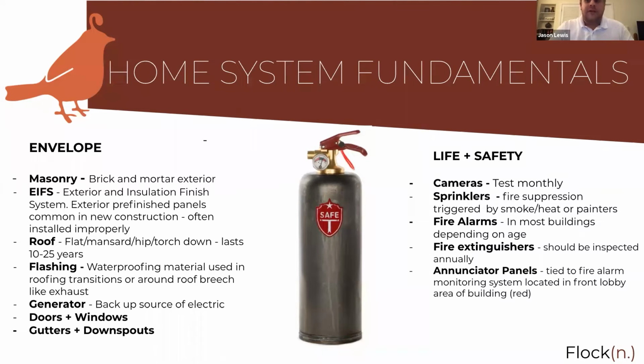For larger properties that we have, I can't stress enough the importance of owner-based maintenance, which we as a community association management company or through other management companies that you have can work for you, where you're conducting visual inspections of the fire system, you're conducting visual inspections of extinguishers, making sure that as we're getting to the colder months, winterization, guys, if you have a dry sprinkler system in level 3 below ground, you want to make sure that you're draining those out. If anybody was a property manager and living in the area during the winter vortexes that hit 6 or so years back, I can tell you that it is paramount to do that.